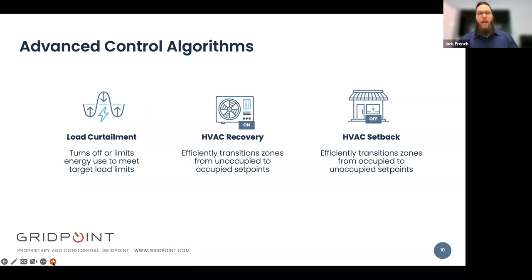So HVAC recovery helps by giving sort of a stair step between your unoccupied settings. So if I'm using the cooling anecdote we talked about earlier, if we have an unoccupied cooling set point of 80 degrees and we need to transition down to 74 by the time folks arrive, HVAC recovery can learn the slope. So how many degrees change over time for each of the zones, and only run the unit for as long as it needs to get within a few degrees of set point. So this is a good way to slowly turn things on, a dynamic control strategy.